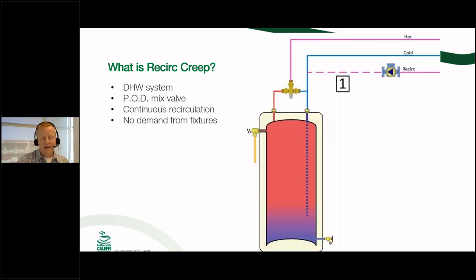So again, you're going to need a domestic hot water distribution system. You're going to need a point of distribution mixing valve, like what we've got up here on top of this tank of this very, very simplified drawing here. And again, you're going to look at continuous recirculation, meaning that recirc is running 24 hours a day, 7 days a week without stopping, okay? And then the last piece of this puzzle is the fact that you are going to have this long period of no demand from your fixtures. So again, typically overnight, or maybe the building's unoccupied for the weekend or for a day, for a holiday maybe, things like that. And the scenario here is that during that time of inactivity, the mixing valve's not getting cold water anymore. Okay, your recirc, which if it's sized appropriately, that's a whole other ball of wax to go into, a whole other tangent to go down, or road to go down.